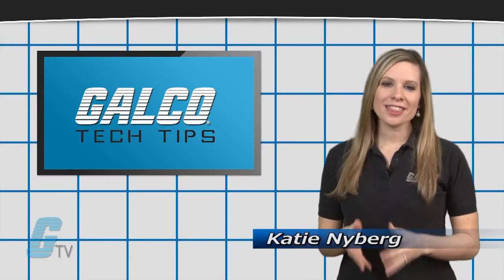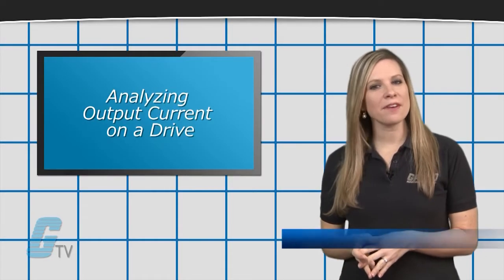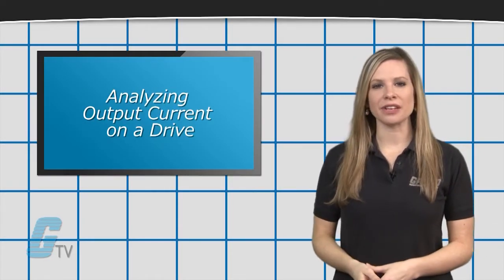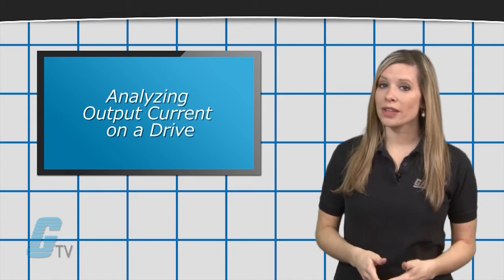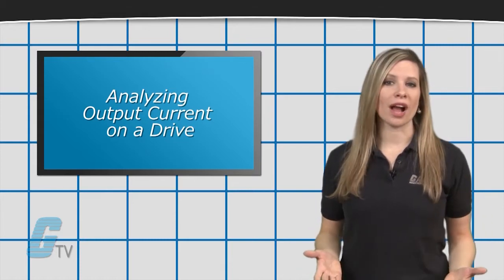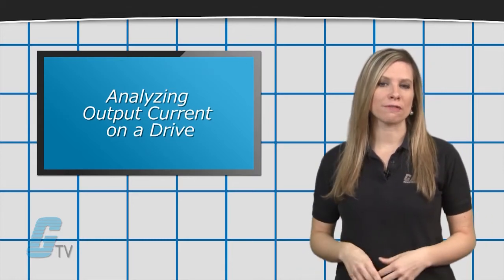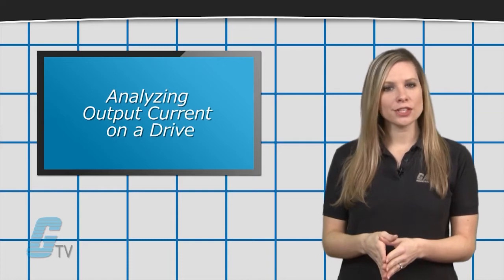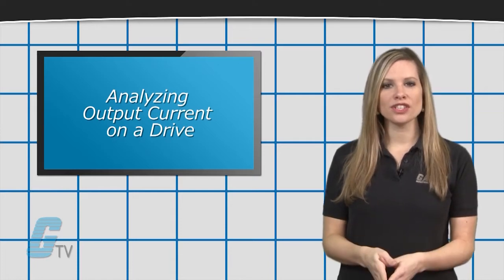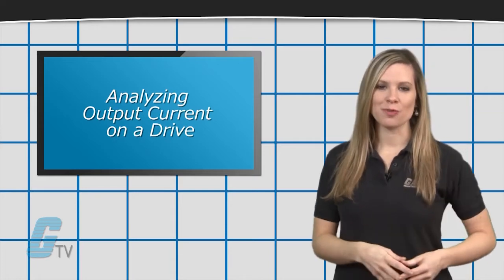Hi, I'm Katie with your GTV Tech Tips. If a motor is clearing fuses, running rough, or the AC drive is producing overcurrent faults, then you may need to check the voltage and current going into the motor.